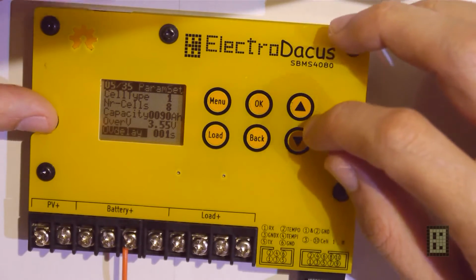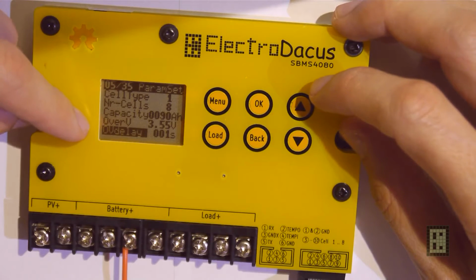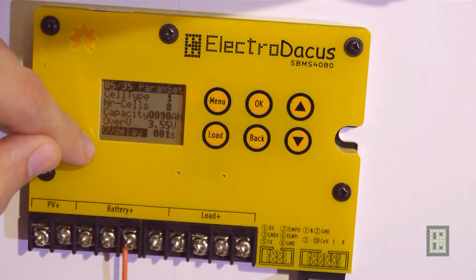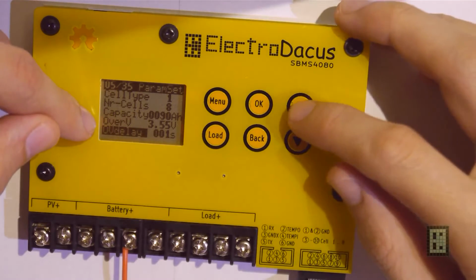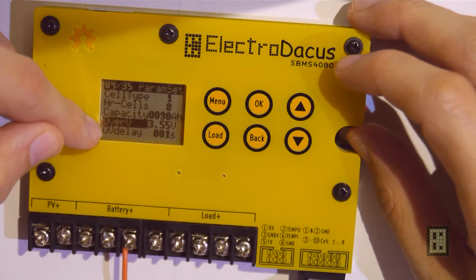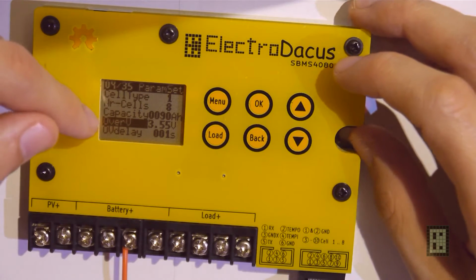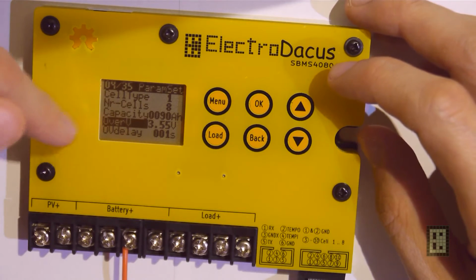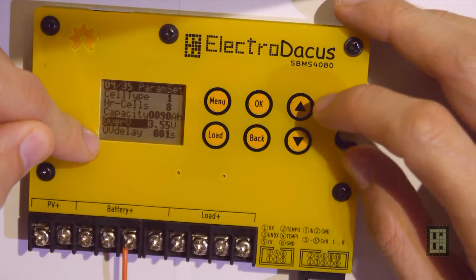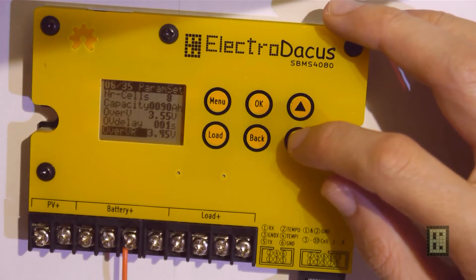So this is the over voltage delay, meaning that it will wait, it's in seconds, so it will wait for 1 second after this threshold was exceeded on any of the cells, and then it will disconnect the charging.